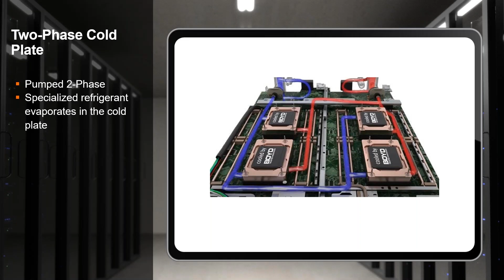From a system geometry standpoint, this is a bit different. You'll have a refrigerant reservoir and a refrigerant pump, which pumps that fluid up through a refrigerant valve and into these cold plates. We use different types of cold plates, some with mini channel evaporators, others with fins inside, where a reservoir of that fluid comes in and starts to vaporize in that space.